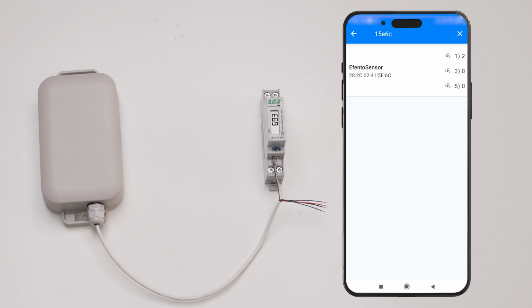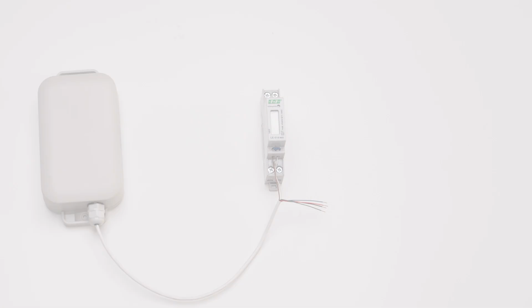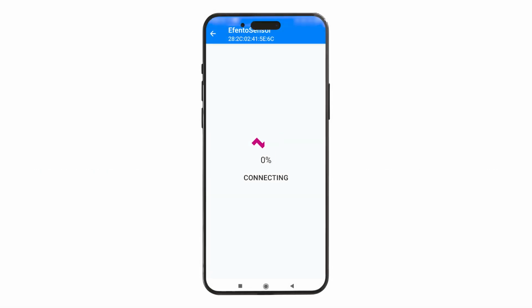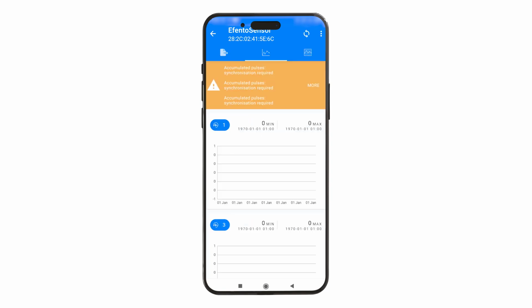The refresh rate of the pulse counter displayed in the application depends on the measurement period settings. By default, it is set to 5 minutes, meaning the counted pulses will be updated every 5 minutes. The configuration of the pulse counter is done using the Efento mobile app. Upon startup, the sensor will report an error because manual calibration is required for the device to function correctly. This involves setting the initial value of the counter, from which the device will start counting pulses.